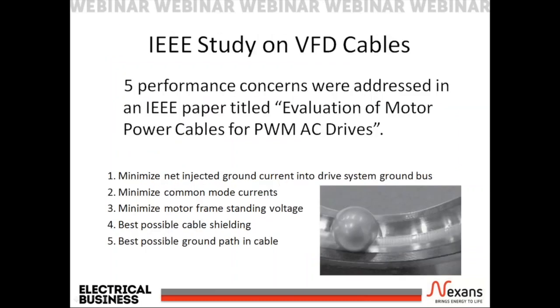Back in 1996, a group of ABB engineers conducted a study which was published in an IEEE paper titled Evaluation of Motor Power Cables for PWM AC Drives. Even though the study is over 20 years old, it is still considered a reference study when it comes to VFD cables. This study looked at 8 commonly available cables which were used to connect the VFD to the motor, focusing on 5 key performance concerns.